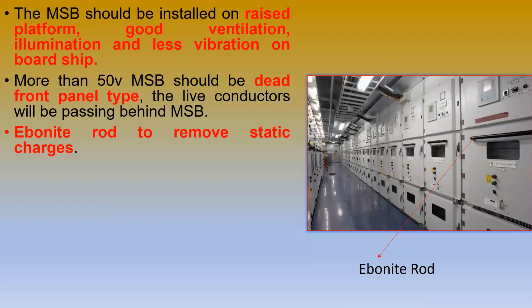So on board ship, mainly in the cargo tanks, because of the movement of the liquid inside the tank, static charge can be formed. And while cleaning the tank, static charge can be formed due to the water forced at pressure. So static charge is nothing but the electrons revolving at the outermost orbit starting to exchange themselves. So there will be some excess amount of electrons, or some deficiency of electrons. This imbalance of the charge is said to be a static charge, which is present stationary at a point. It is very dangerous. This may lead to spark, ignition, and explosion also.